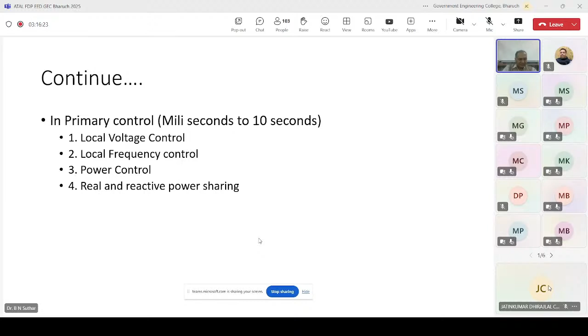Now let's see how this control mechanism works, and what are the functions of all this control. In primary control, it has to control four things: local voltage, local frequency, and real and reactive power, meaning basically the power factor - what should be the amount of real power and what should be the amount of reactive power. This is for a particular generating RES - one primary control for PV, one for wind, one for ESS. We have already discussed this in the previous figure.